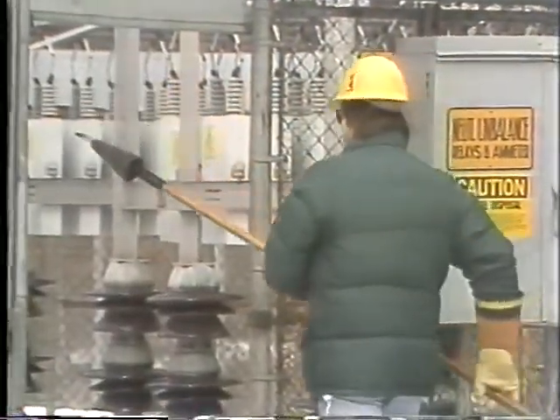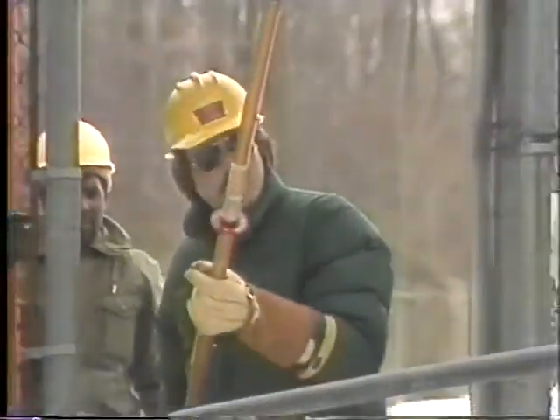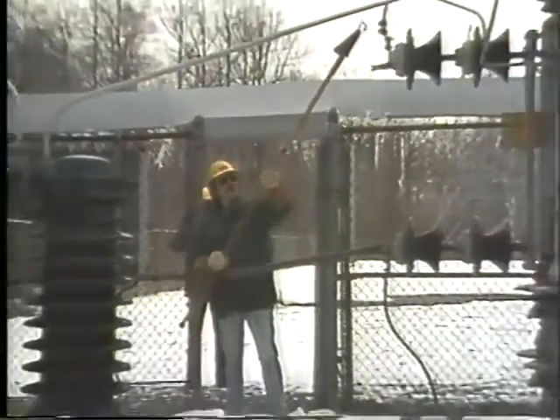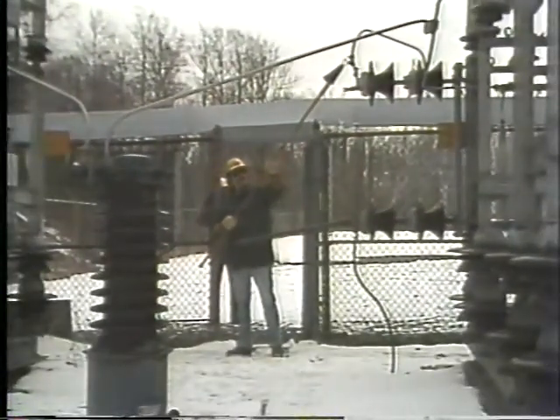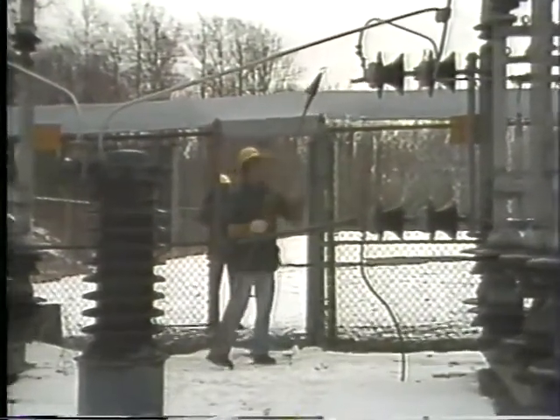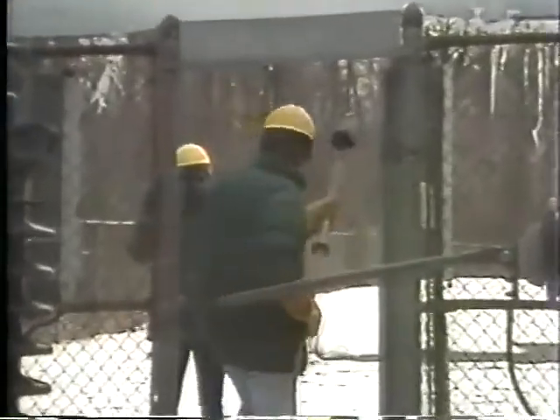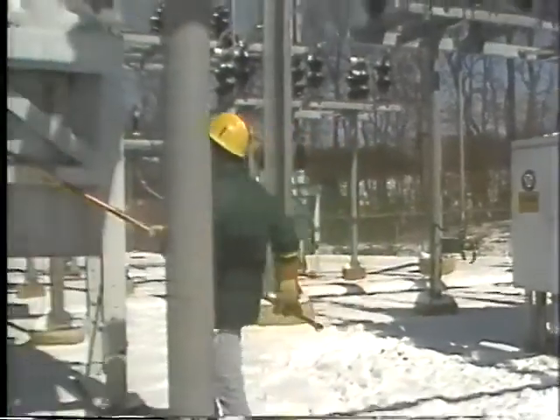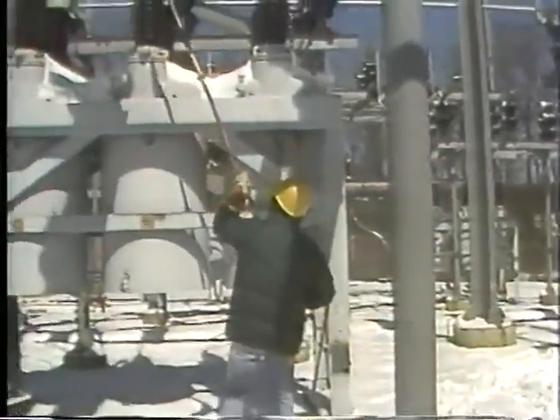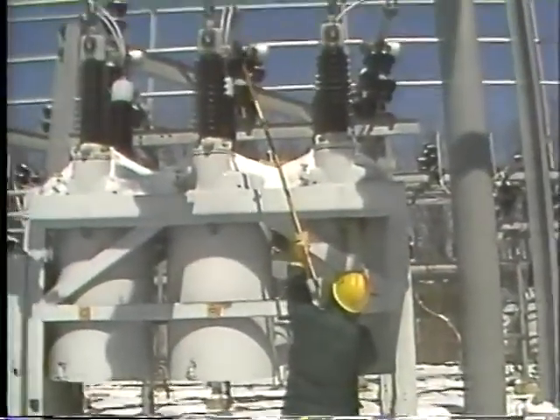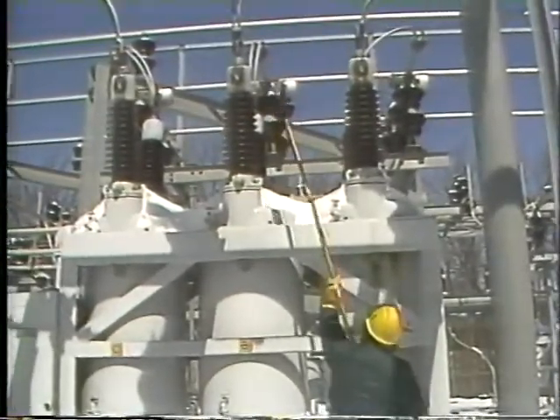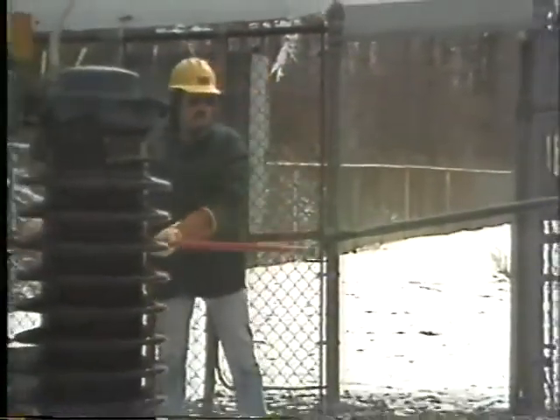To make sure that the bank is de-energized, he checks it with the glow tester. It shows no indication, which means that there's no AC going to the frame. It doesn't mean that the capacitors are completely discharged. Just to be certain that his detector is still working properly, he tests it again on a source that's known to be energized. The next step is to ground the frame of the capacitor bank.